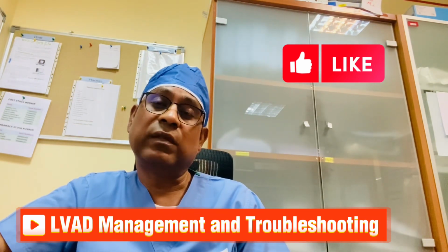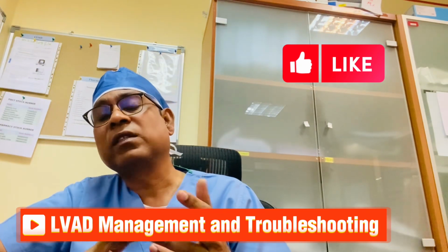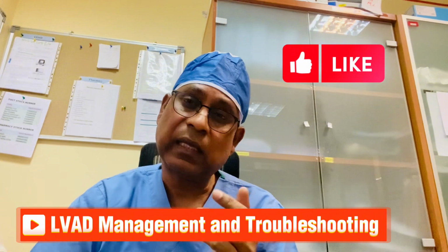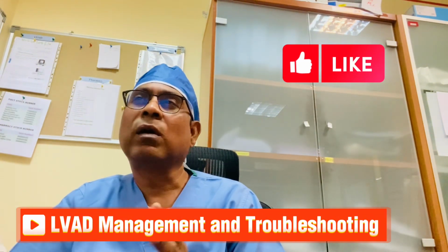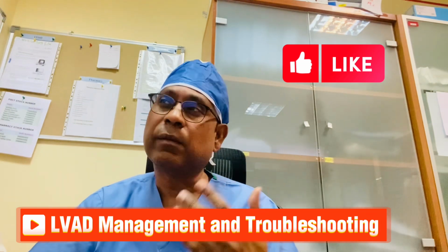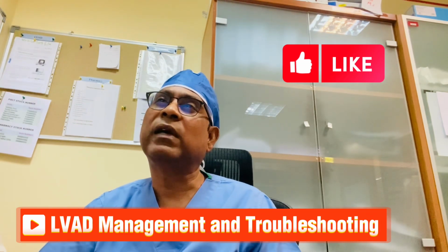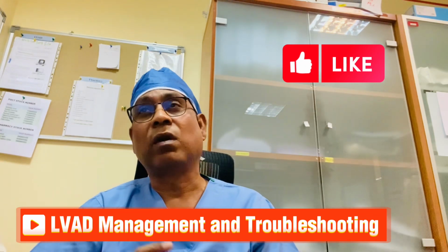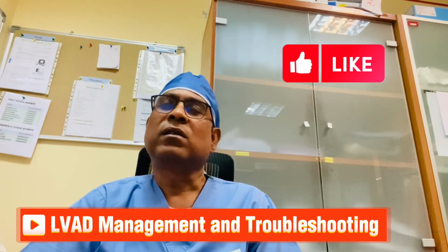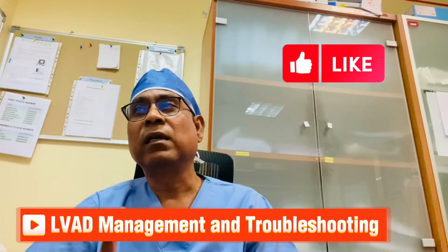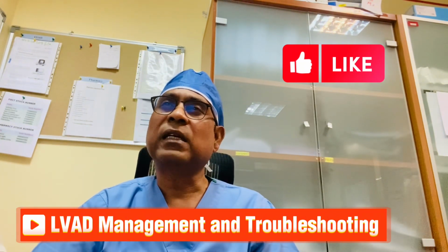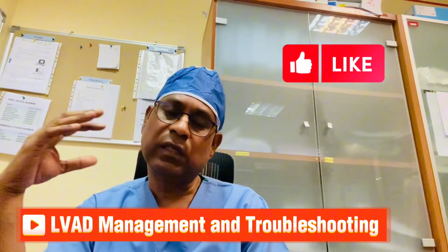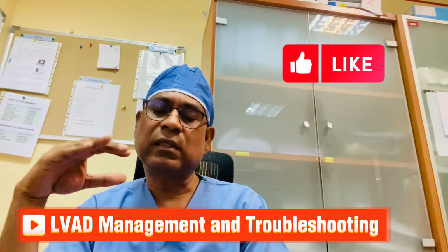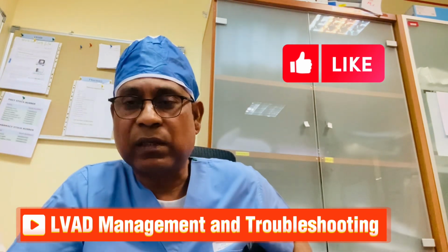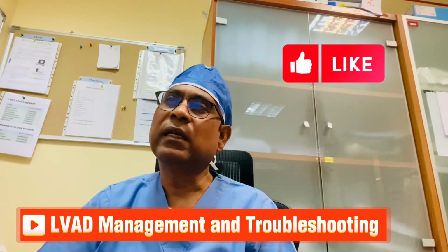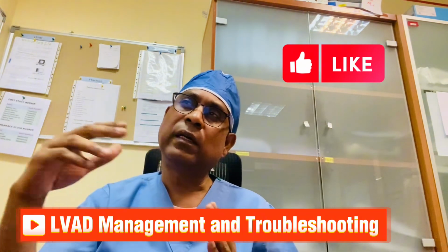The pump parameters. When we talk about the LVAD parameters, the first parameter you have to focus on is your pump flow, the amount of blood flowing through the VAD, displayed as liters per minute. It is actually a calculated value based on the speed, and fluctuation is normal. Now what is speed? The speed is how fast the VAD is rotating, in revolutions per minute. The fixed speed is set on the system by the VAD coordinator with the team of the cardiac surgeon. And HeartMate may fluctuate from 150 to 200 RPM.